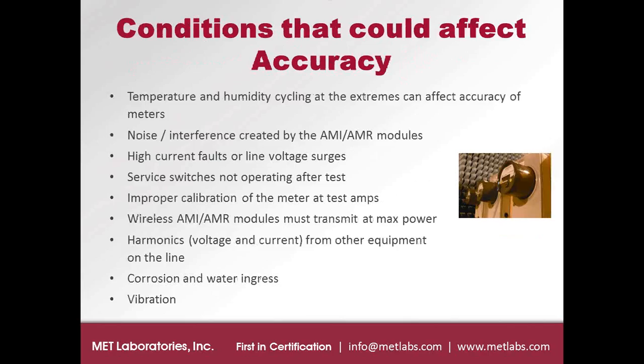Some of the conditions that affect the accuracy that we see here: the temperature, humidity cycling, particularly at the extremes, can cause the meter to wink out and no longer be functional. Noise or interference created by the communication modules internal to the meter, we've certainly seen those problems. The current faults or line voltages many times may cause issues. Service switches seizing up and no longer becoming functional or even fragmenting at times. Improper calibration of the meter at test amps.